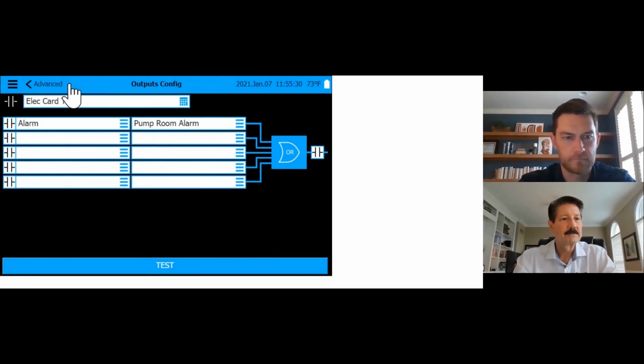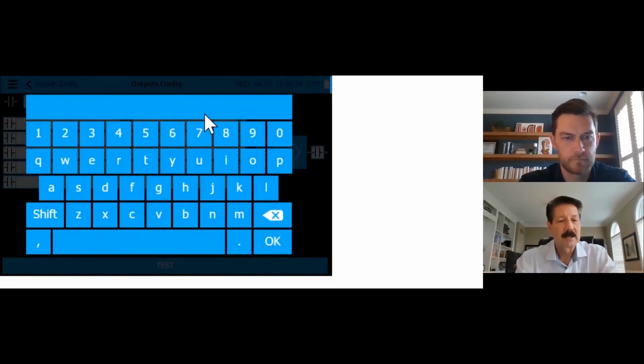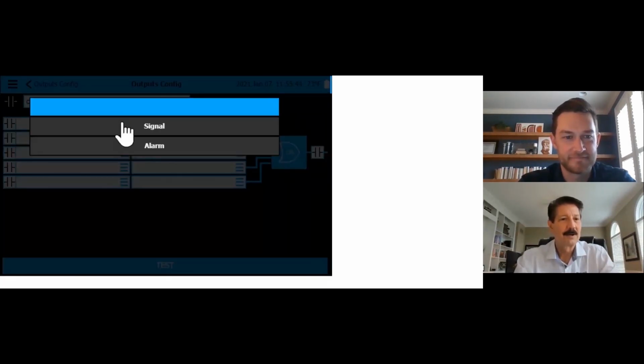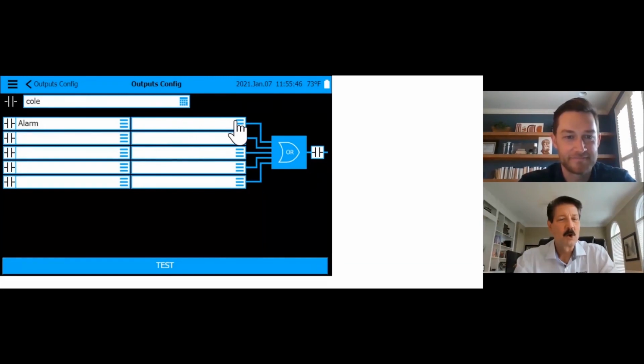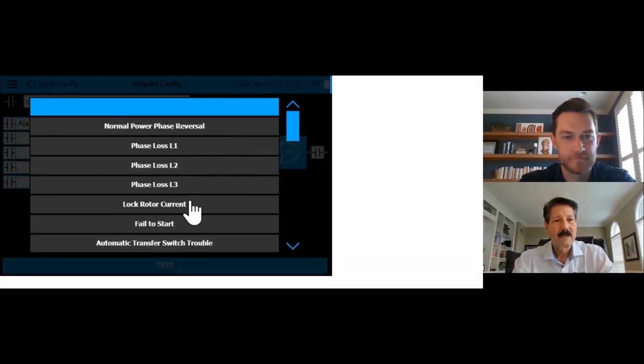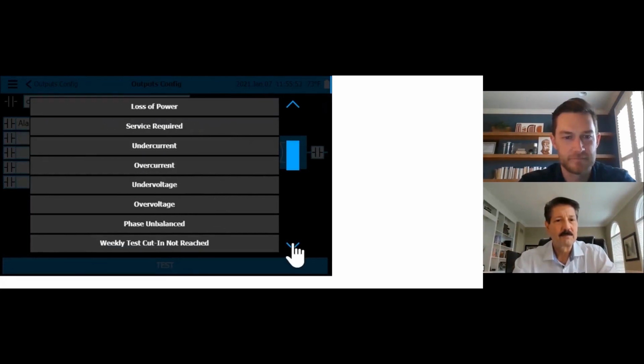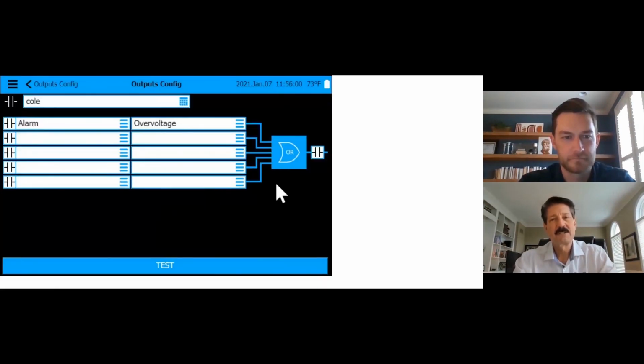For the sake of doing this, let me go to TB6. You could sit there and change this, and I can call it cole. Well, I'm going to type this in. I can type in cole. So this contact's going to be called cole, and it's an alarm. And so what we're doing here, you see on the left side, it's an open alarm. And let's just do something here. We're going to make it an over voltage condition, which typically is pushing close to 15%.